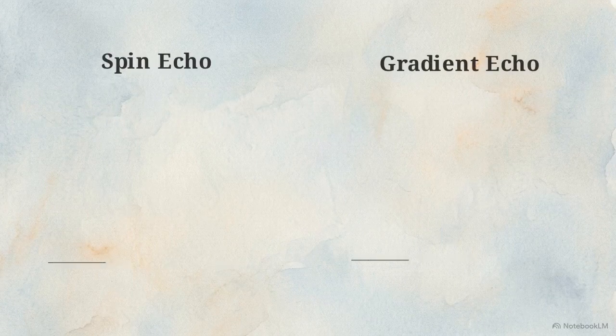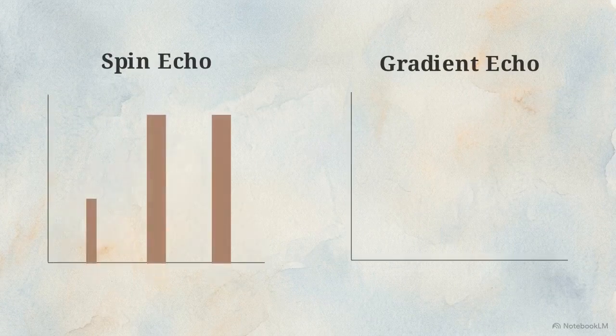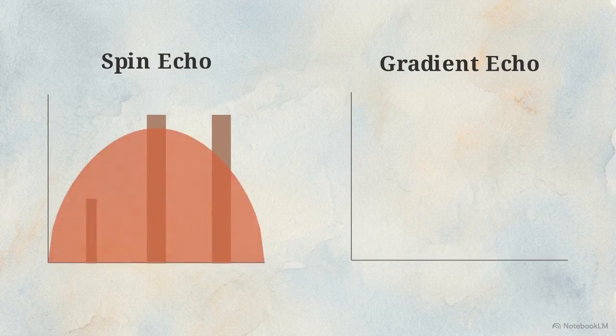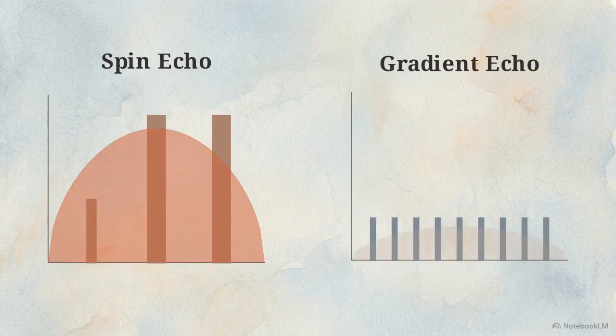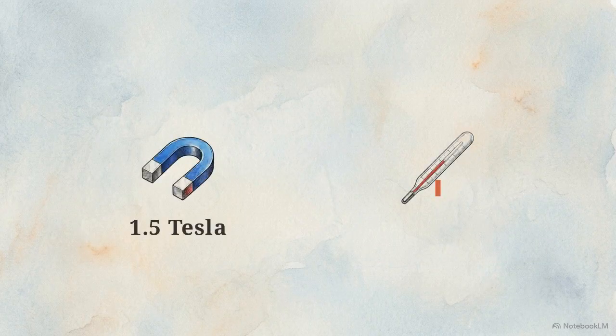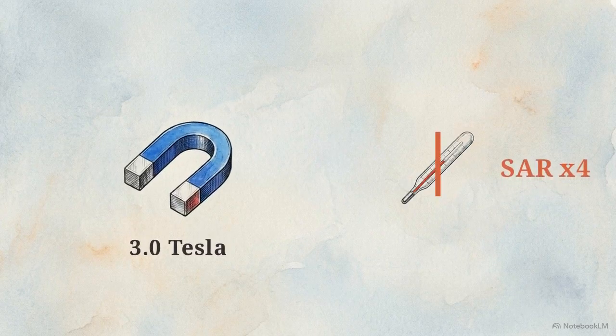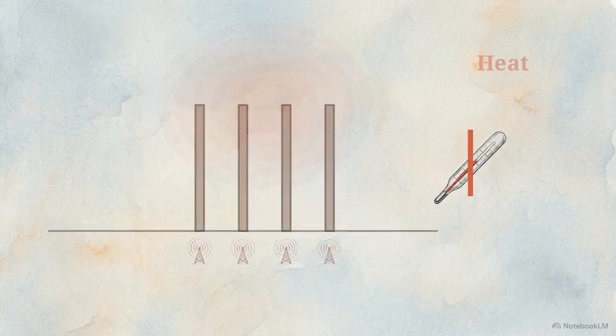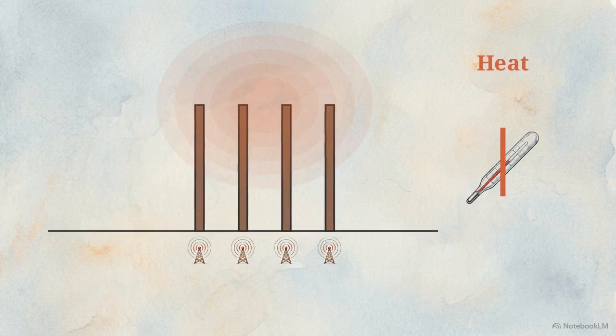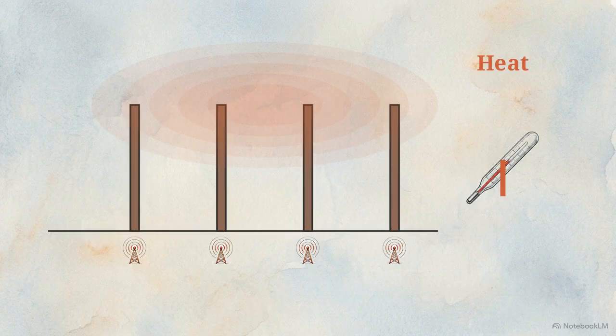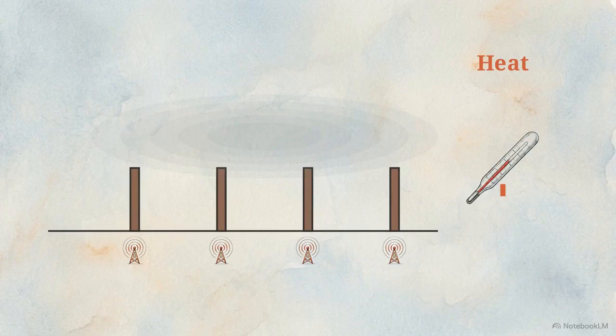This comparison shows the energy requirements of different sequences. A spin echo sequence uses large 180-degree pulses that result in high energy deposition, whereas a gradient echo sequence uses smaller pulses with a lower net thermal load. Field strength also scales the risk. Moving from a 1.5 to a 3 Tesla scanner results in a 4-fold increase in the specific absorption rate. To reduce SAR, operators can increase the repetition time, spacing out RF pulses to allow the body to dissipate heat. Alternatively, they can reduce the flip angle to 90 degrees or less, decreasing the energy payload of each pulse.